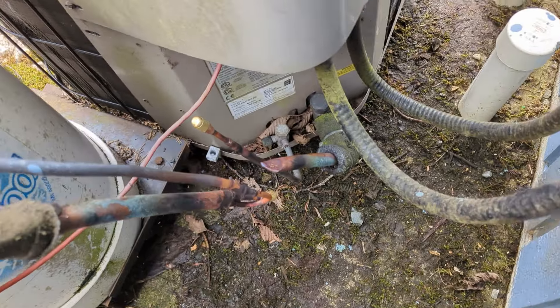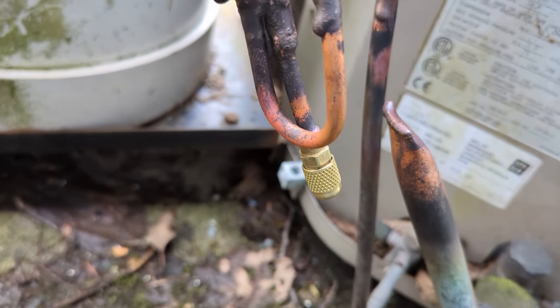Another super interesting job we had this week was at a salmon hatchery, where they've got a system that keeps the water at 10 degrees Celsius, which is a very strange temperature. They have what used to be like a pool heater there, but it was able to go down to that low temperature. So what we have there is a refrigerant leak. What we ended up doing was isolating the condenser and the evaporator so they were both separate. We pressurized both sides with nitrogen and left it there for a few days — we were there on Thursday. We're going to go back either Monday or Tuesday next week to see if our pressures are different. The hope is, fingers and toes crossed, that the leak is in the condenser and not the evaporator. Anyway, I'll tell you all about that in a bit.